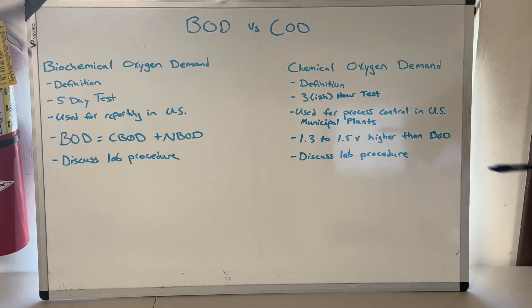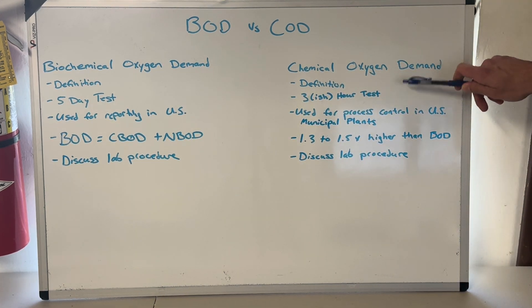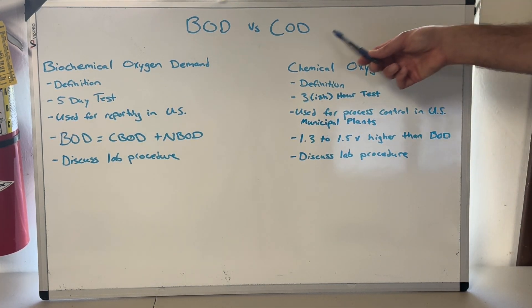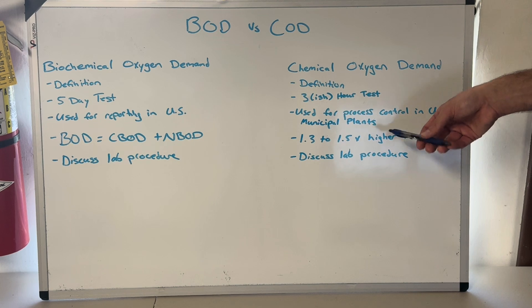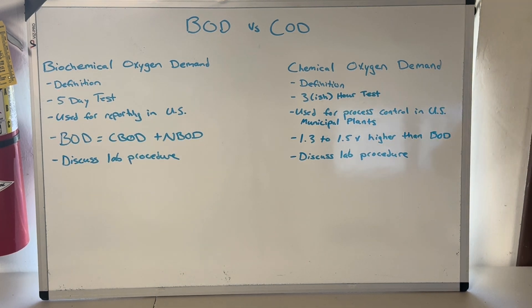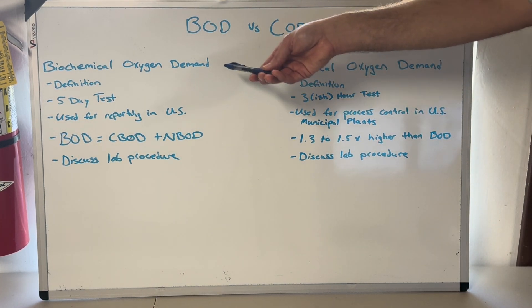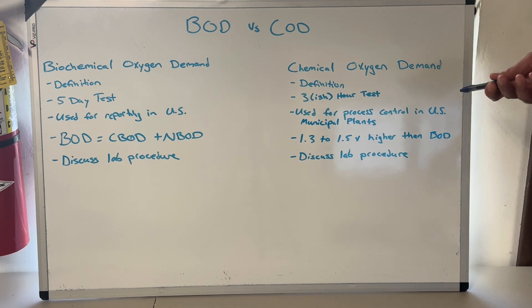The five-day BOD test is the official test used for reporting in the US for municipal waste. The three-hour COD test is used for process control in large US municipal plants — you're not going to see it much in a hundred-thousand-gallon-a-day plant, but you will in a hundred-million-gallon-a-day plant. COD is also heavily used in industrial plants. A paper mill, for example, has a lot more COD constituents to look for than a municipal waste stream, because you're not dealing with organic waste but with other chemicals that need to be stabilized before they go out into the environment.